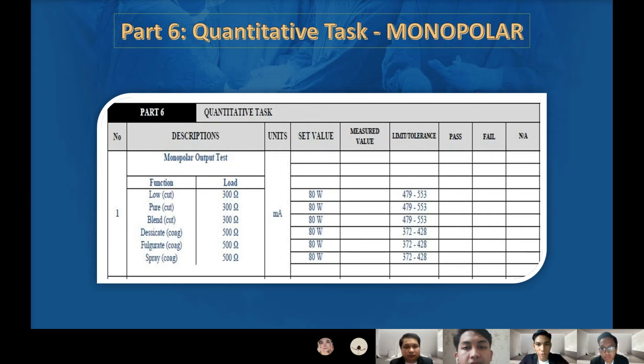For the function, we have two: cut and coagulating. In the cut, we have low, pure, and also blend, where we put the load at 300 ohm and set 80 watt, and we measure a range of about 479 to 553. For coagulating, which is desiccate, fulgurate, and also spray, the load is 500 ohm, we set the value at 80 watt, and the measured range is 372 to 428. All these rated values are based on the service manual for this device. All right, thank you. That's all.